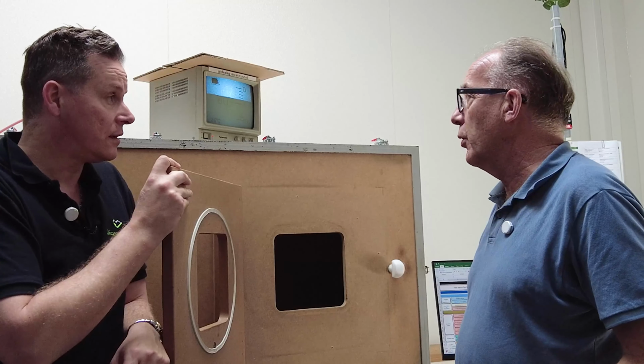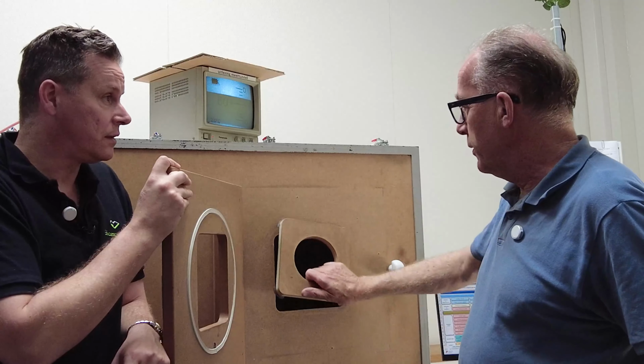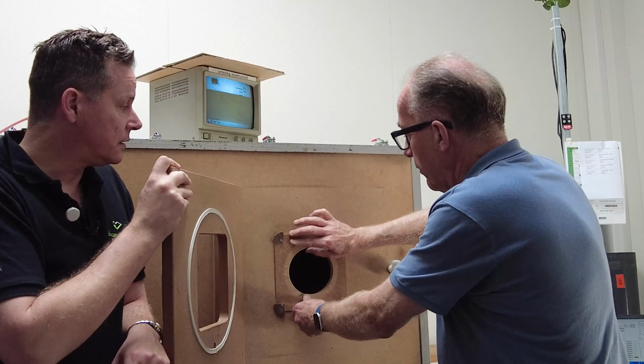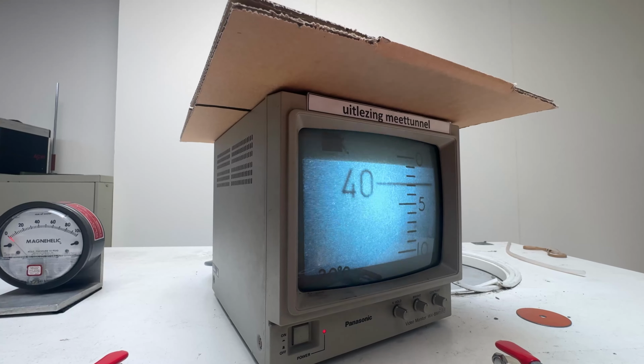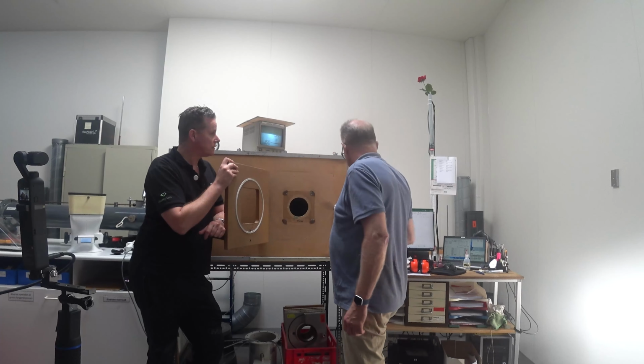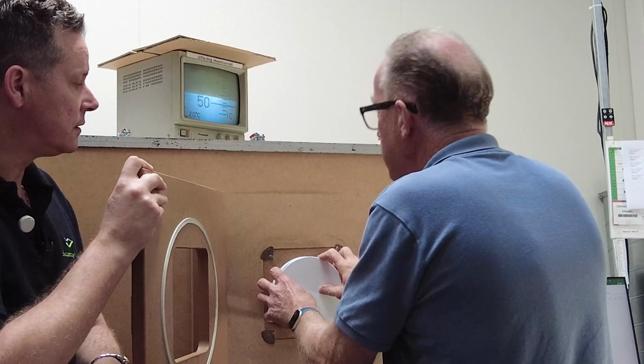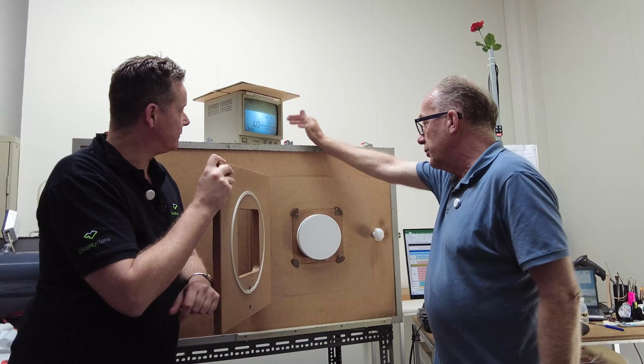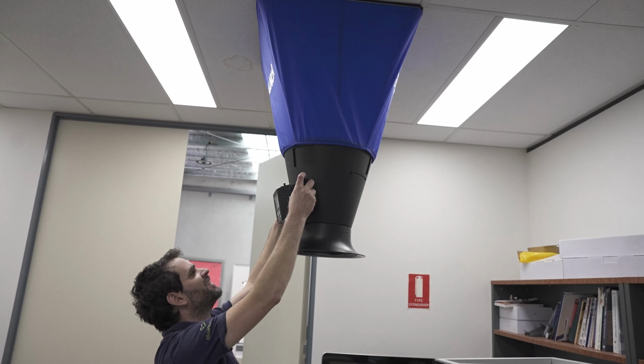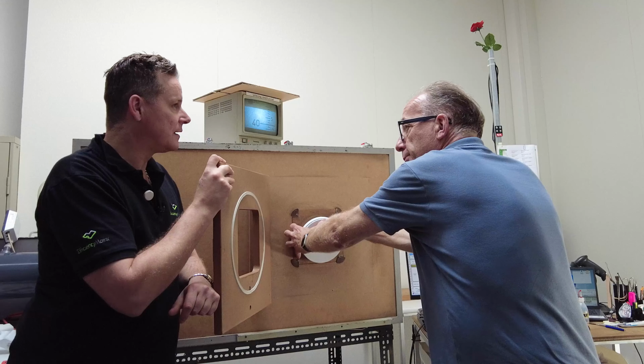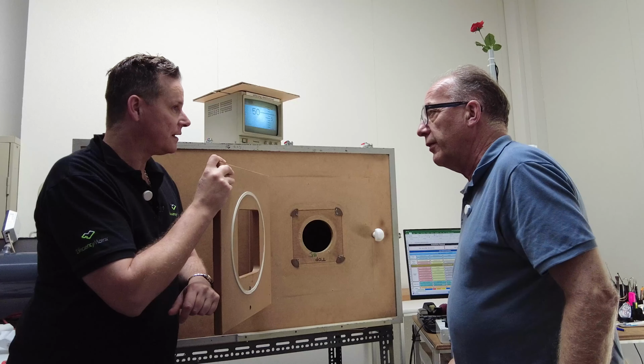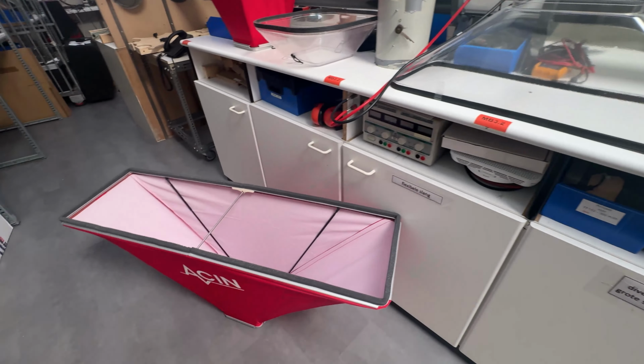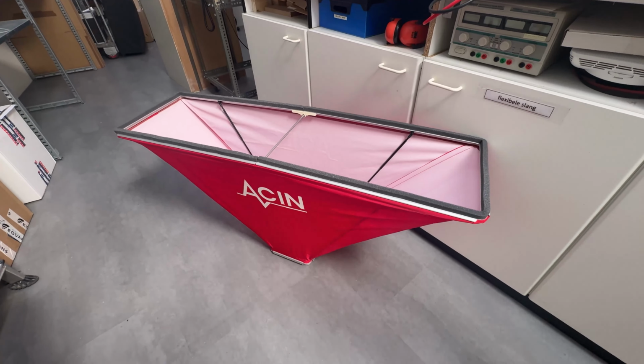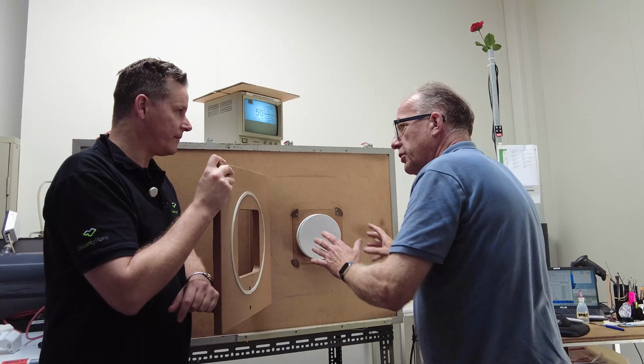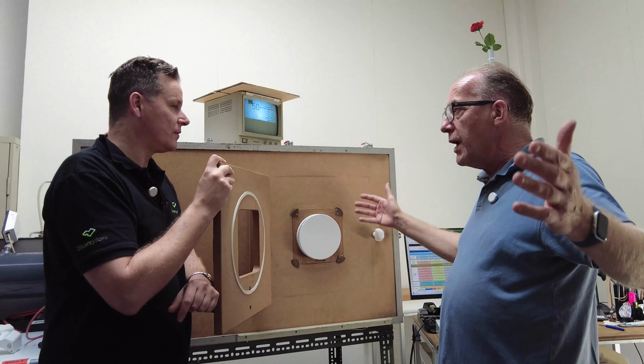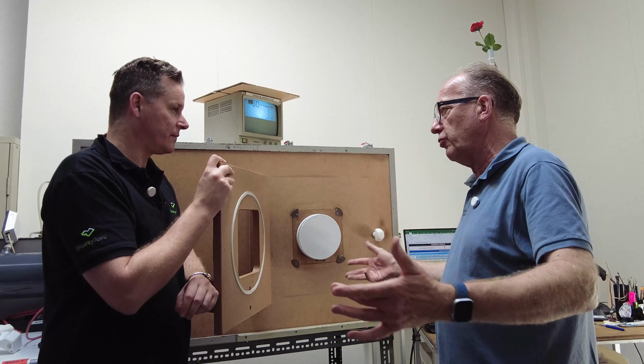So this is the flow at the moment, coming through the tube. I'll put some resistance on it. There it goes. Flow goes down. And now I put this one on, so now the flow is even lower. But now I put a passive flow hood on. On this one, the effect will be small. But on this one, the effect will be very large. Yeah, gotcha. And with the Flowfinder, it doesn't matter. It measures this one properly, and it measures the open hole properly. Cool. So it does a whole range of resistances and grills without pain.